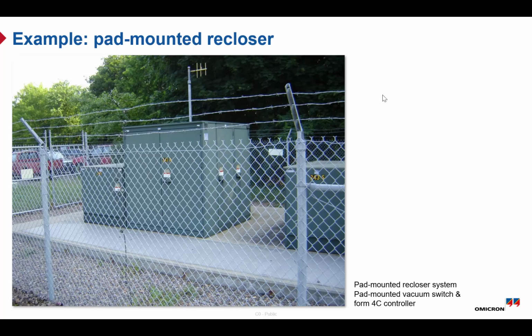You will typically find the equipment enclosed within a fenced area. This is mainly for safety, to prevent unauthorized access or accidental contact. Functionally, it works exactly the same as the pole-mounted recloser, providing protection, fault interruption, and automatic restoration. The difference is mainly in the installation style and accessibility.